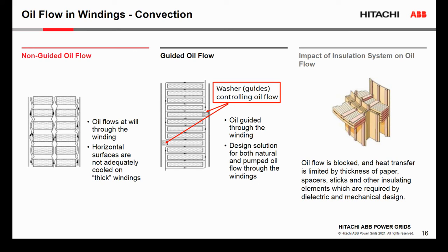And we designed the zigzag oil flow circulation. So every several discs or turns, we install the oil guides inside and outside. And with this solution, we force oil to go in between the discs and between the turns. And this will reduce significantly the gradient between oil and the windings.